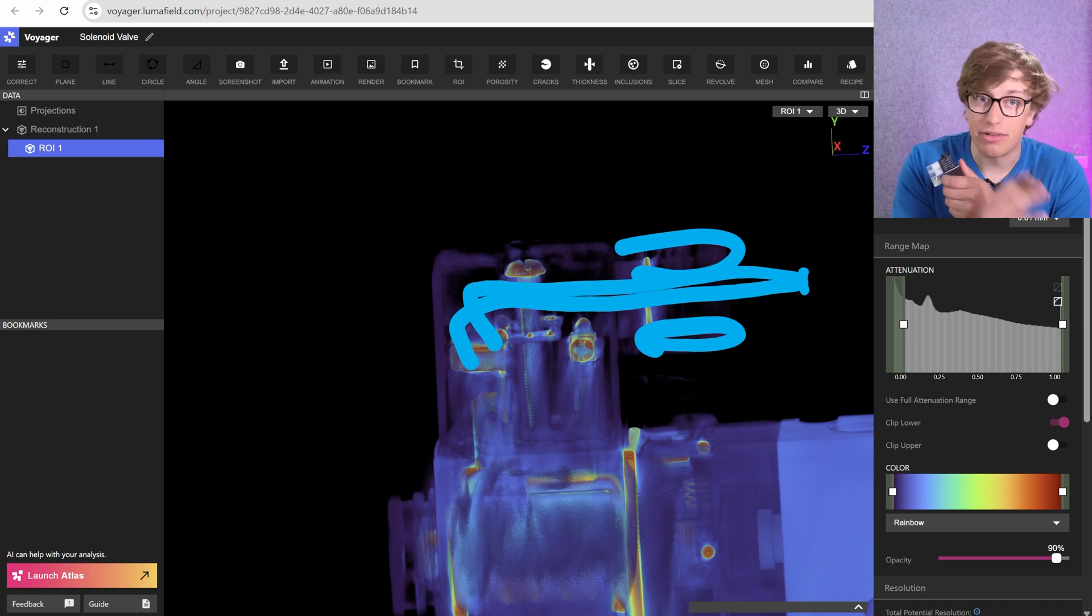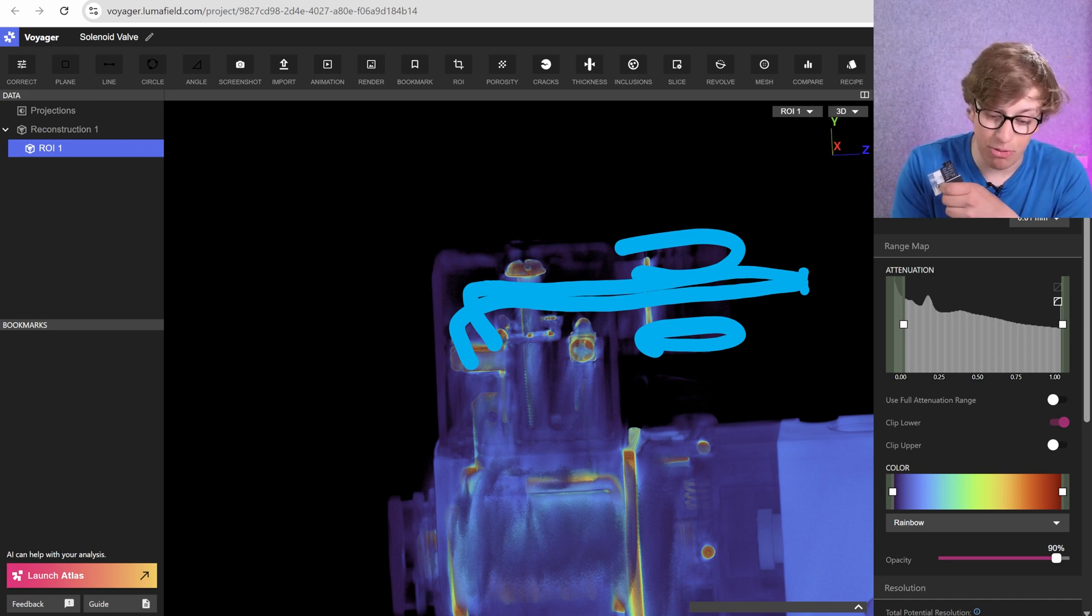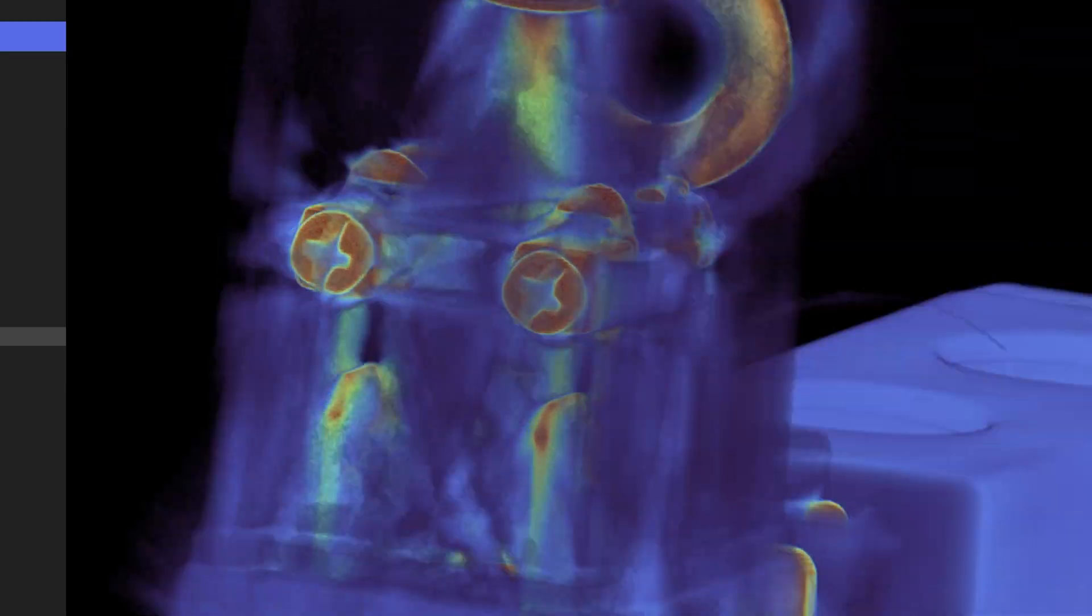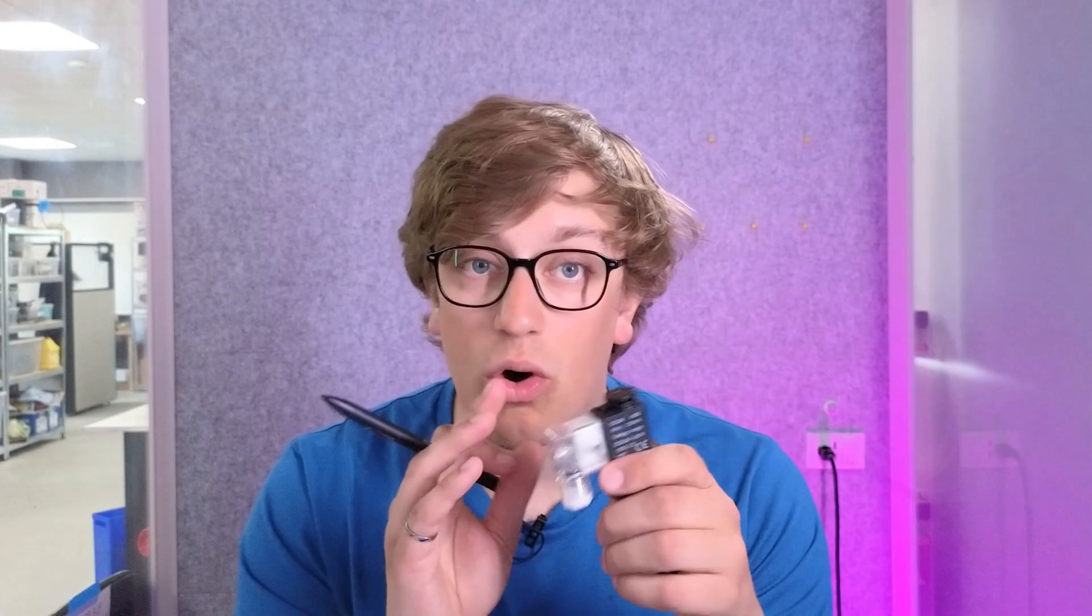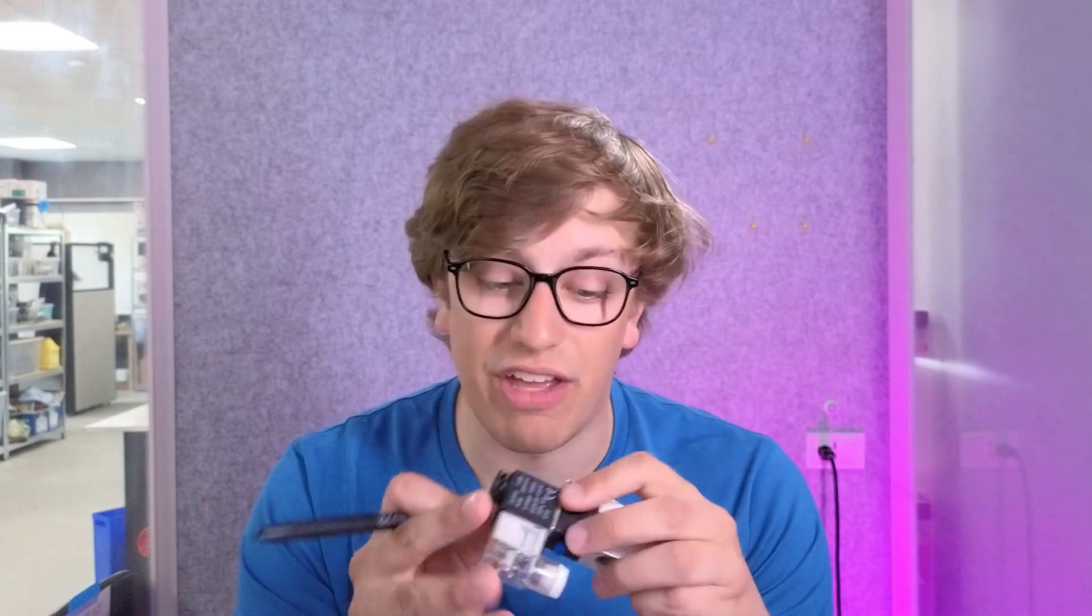Positive, negative, and protective ground. This happens to be a 24-volt DC solenoid on this valve. What that means is that you want to apply 24 volts between this terminal and this terminal, and that will change the valve position.